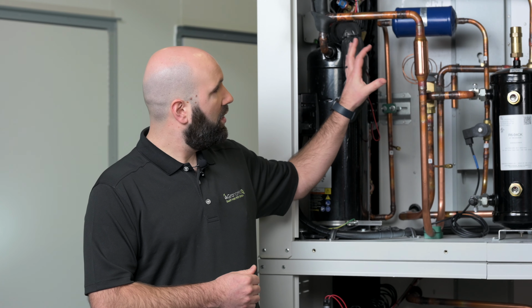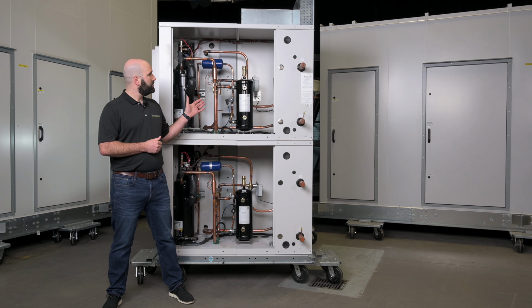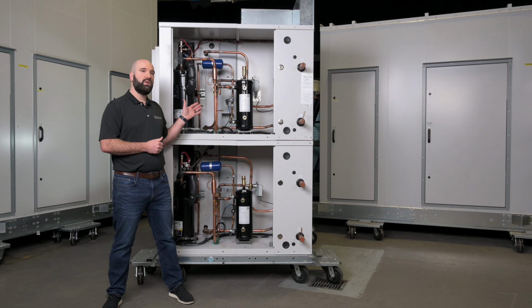TX valve, all of the coil sets, all the major refrigeration components are in this mechanical vestibule, which means that you can open the doors to that mechanical vestibule. You can do the maintenance on that system without interrupting your airstream. Without interrupting the operation of that unit, you can adjust the TX valve, for instance, while still having nominal flow through your coil set, allowing you to much more quickly find the sweet spot for that unit. It also means that you don't have any risk of contamination between your mechanical side and the air tunnel side. Let's spin the unit around now.